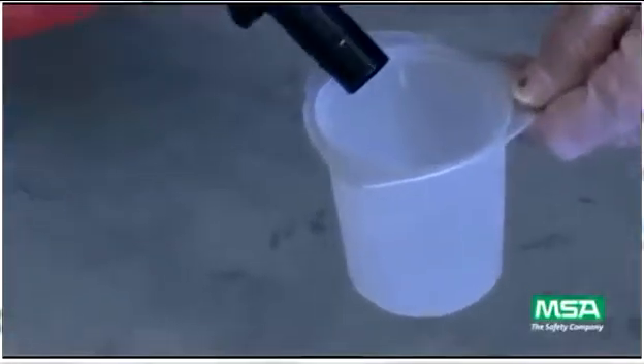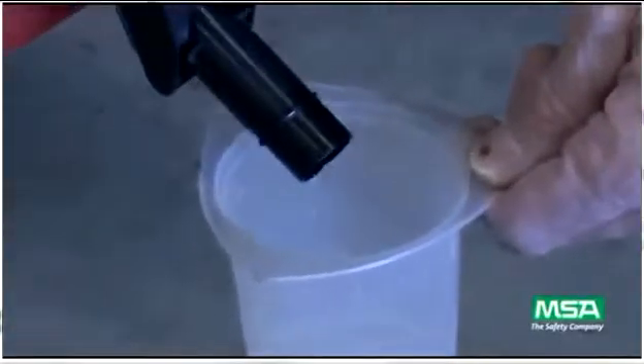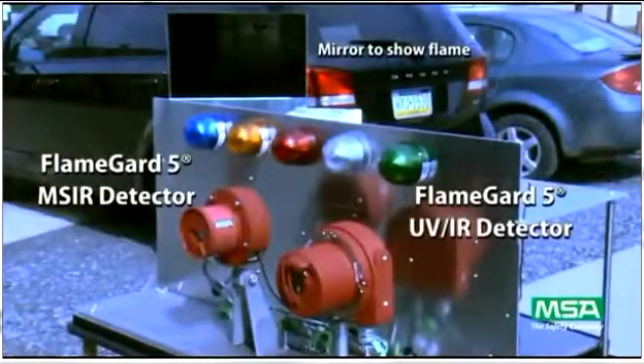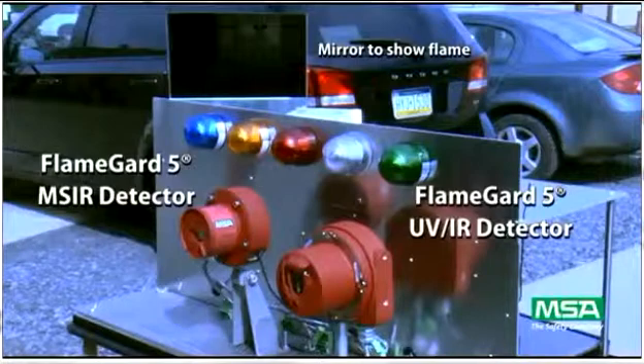All tests were done in our flame building here at MSA using gasoline in a one square foot pan. The exposure of the fire to the detectors is controlled by a pneumatically operated curtain. On the left is our FlameGard 5 MSIR detector and on the right is the FlameGard 5 UVIR detector.